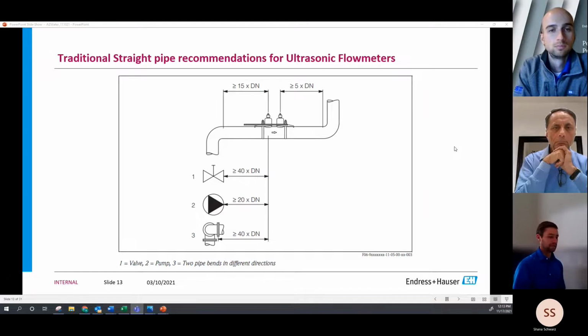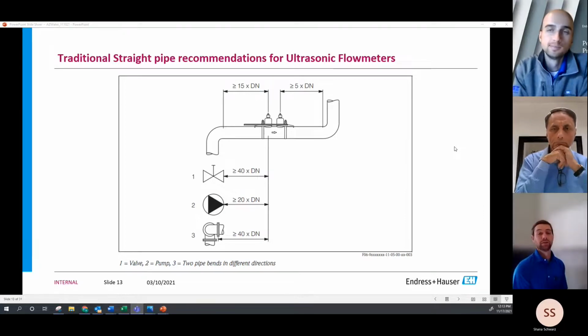So staying along that same logic, that same use case, E&H put some thought into applications where you can't use a mag meter. So anything that has low conductivity, think about ultra pure water, or applications where we can't cut into the pipe itself and get a flow tube in there. Any of those types of applications, you start to look at ultrasonic flow meters, the clamp-on style.